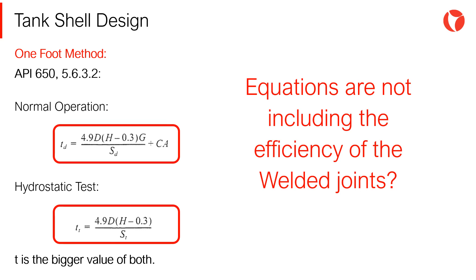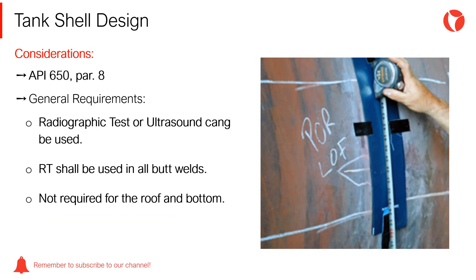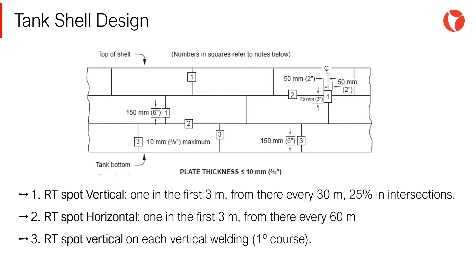For storage tanks, the joint efficiency doesn't adopt a specific value as in the case of pressure vessels. As long as the results of non-destructive examinations required by the API 650 standard are met, joint efficiencies are considered one. Non-destructive examination requirements to determine the reliability of the welded joints are included in the API 650 standard. Taking into account that requirements are many and very specific, the API 650 standard must be consulted in this regard prior to any development.